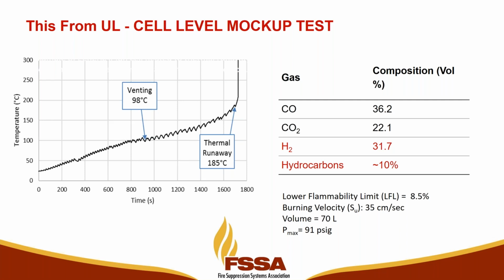Yes, I'd say look at it as an explosion analysis. If you've got the data from your 9540A testing, in general what that says, if I summarize it, is: take a cell, burn it, see what happens. Take a module, burn it, see what happens. Take a rack, burn it, see what happens. Take an installation, burn it, see what happens. But it gets very expensive when you start burning whole installations - you start spending $10 million on a cabinet, and they don't like burning those very often.